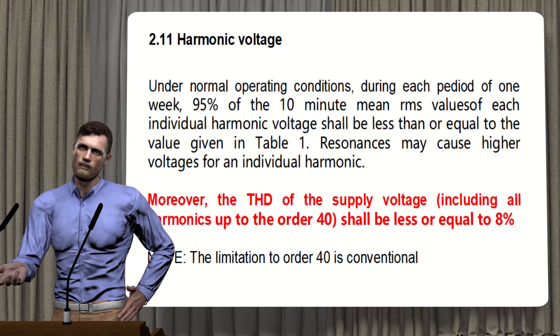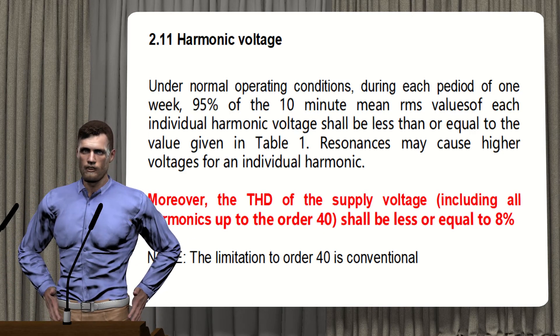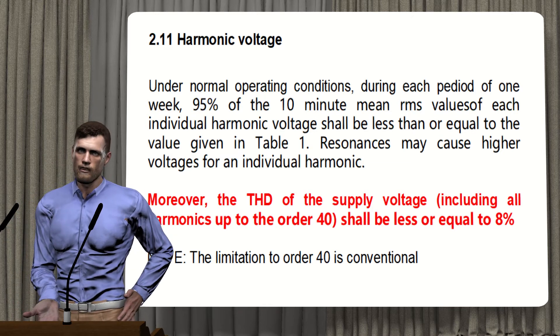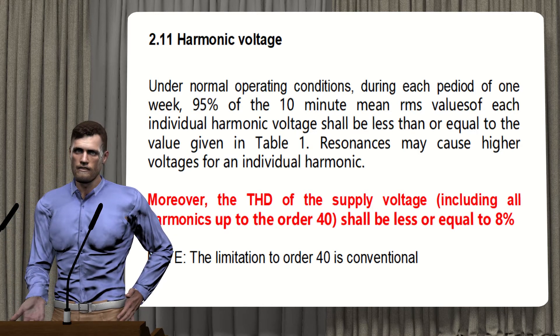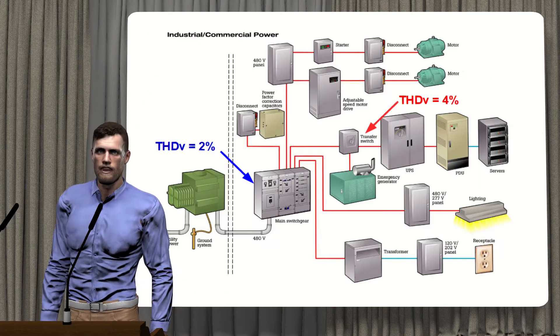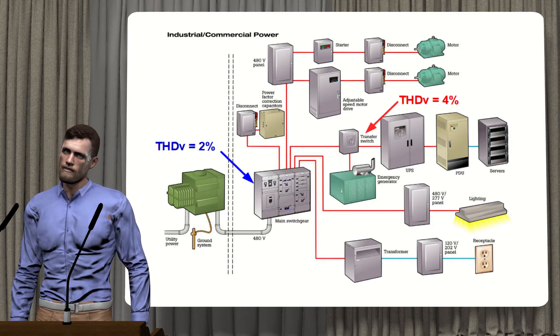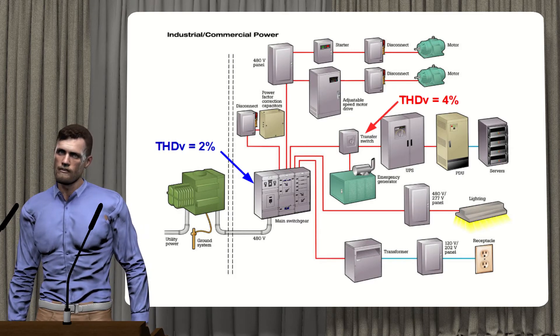If we measure the THD in another point of the installation different from that of the common coupling point, its value may change, since the further we are from the common coupling point, the greater the distortion due to the voltage drops in the distribution cables caused by the current harmonics generated by the loads.